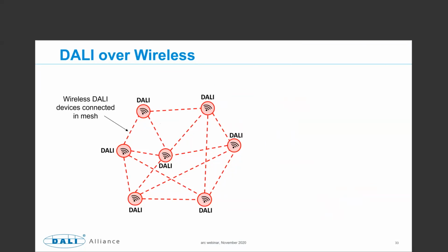Then we look at the other way of doing it, which is DALI over wireless. Here the DALI devices, all of the wireless devices you see, are DALI. This could be a bunch of luminaires in a room or in a system, connected wirelessly, and here they are talking DALI to DALI. There's no translation, no mapping of the behavior. The inherent behavior is DALI, and what we're doing is using the ecosystem partner to affect the communication, much like your mobile phone carries your voice or email via another network. It's the same process here—we're using the other network to carry the native DALI commands from place to place.